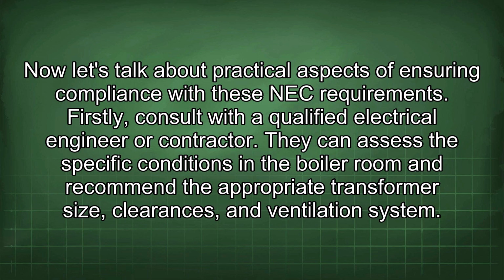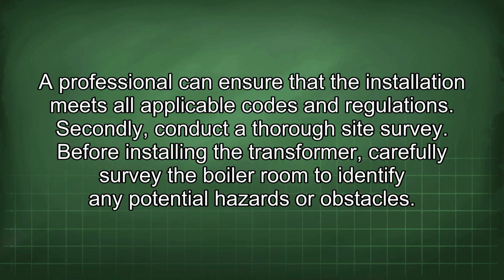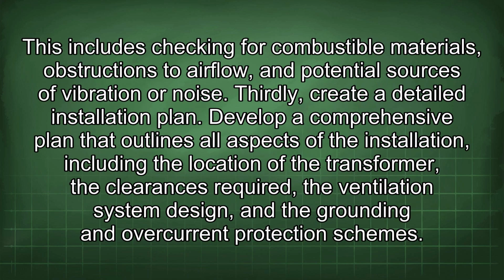They can assess the specific conditions in the boiler room and recommend the appropriate transformer size, clearances, and ventilation system. A professional can ensure that the installation meets all applicable codes and regulations. Secondly, conduct a thorough site survey. Before installing the transformer, carefully survey the boiler room to identify any potential hazards or obstacles. This includes checking for combustible materials, obstructions to airflow, and potential sources of vibration or noise.